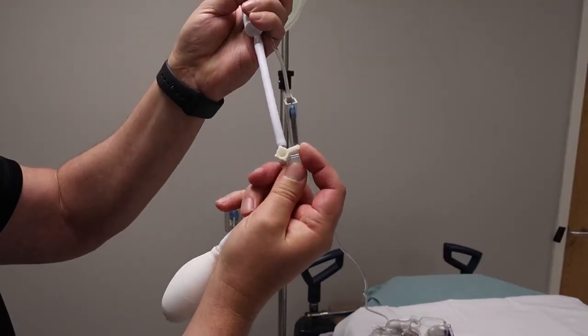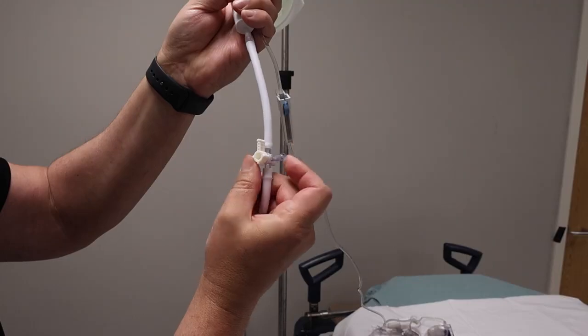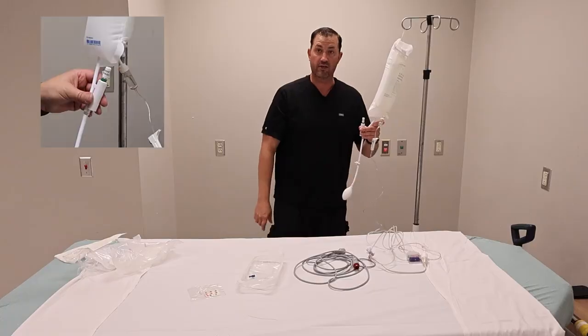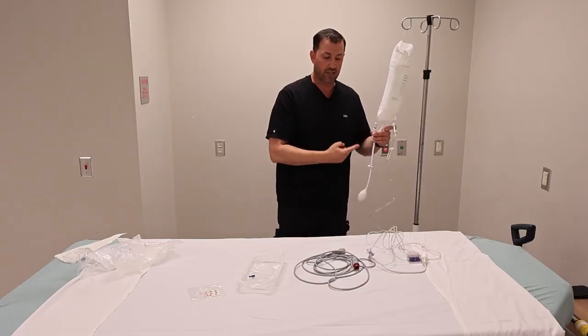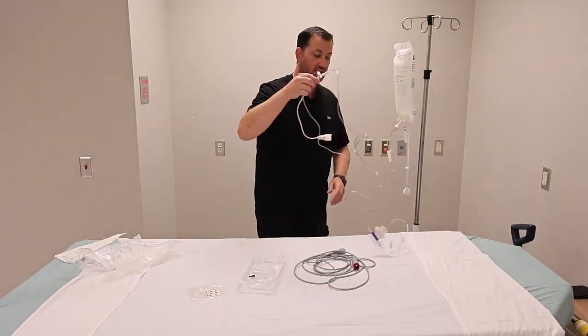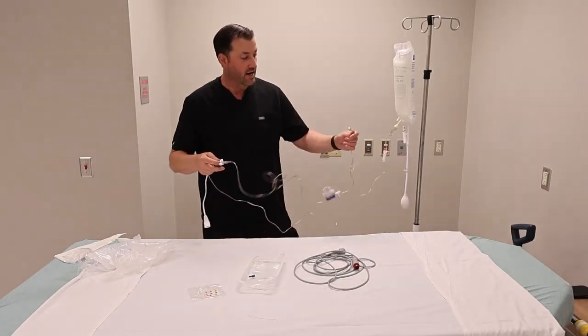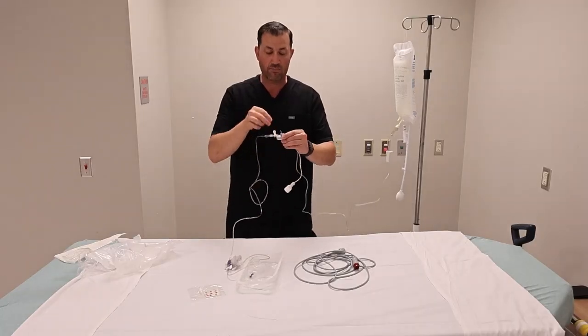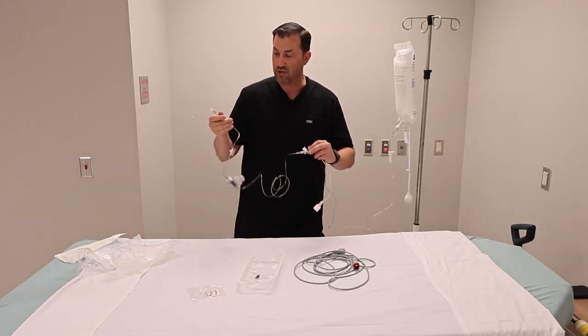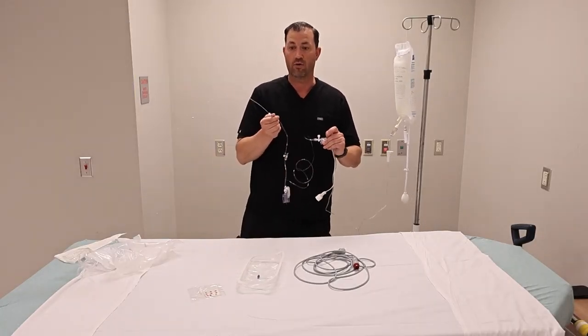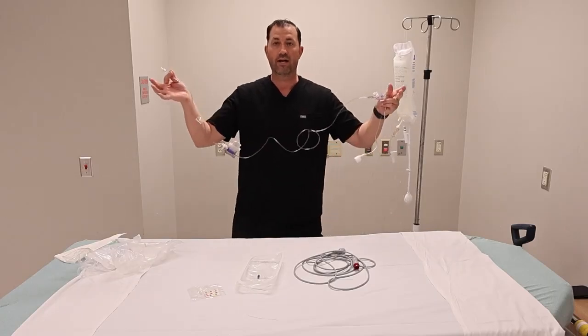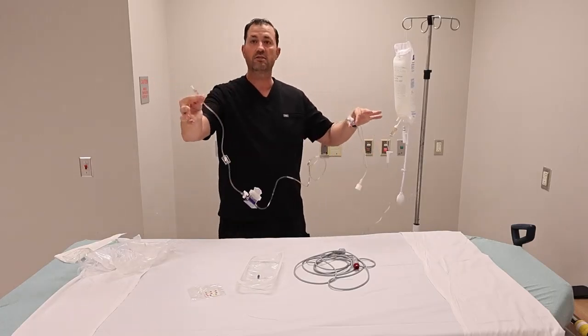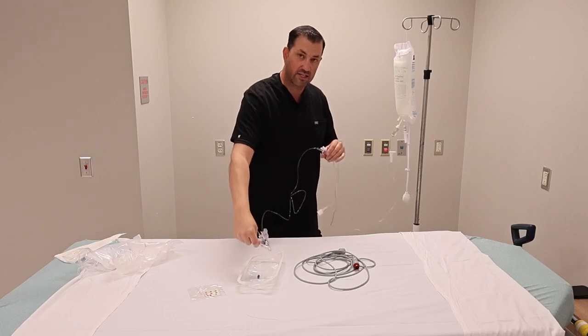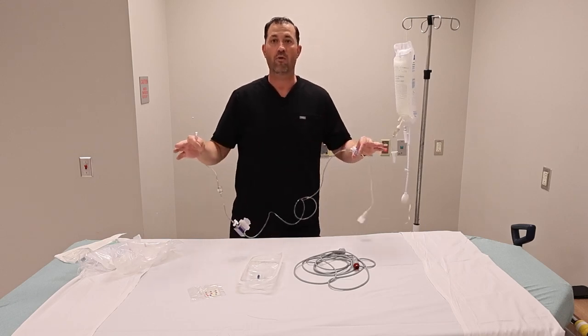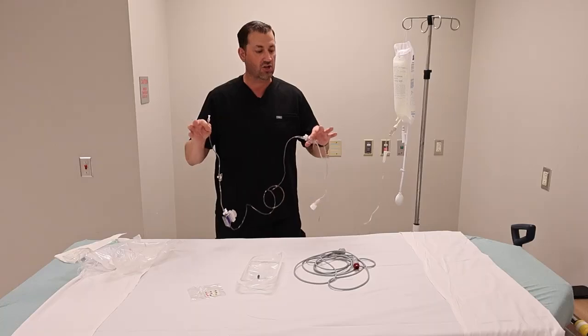Once the bag's fully inflated, move the stopcock up in order to prevent air from leaking out. You see green? Green is good, you're good to go. Now, because you didn't close anything else off, you are ready to prime this line. In order to prime the line, all you have to do is pull this pigtail straight up, and this will shoot water out. Boom. Now you're ready. You can hand this to a doctor, and they can put it right onto the A-line that they just inserted, and you are good to go, no more mess, and essentially your A-line is almost done.